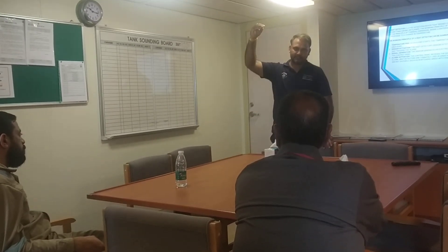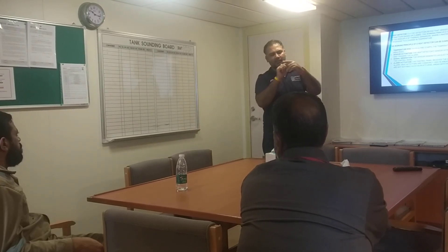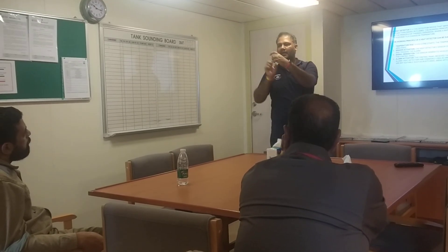The common fixed temperature is around 60 to 65 degrees. If the temperature rises up to 65 degrees, there is a very sensitive material — one plate — and that plate starts bending. It goes from straight to bent, and that change triggers the alarm signal.